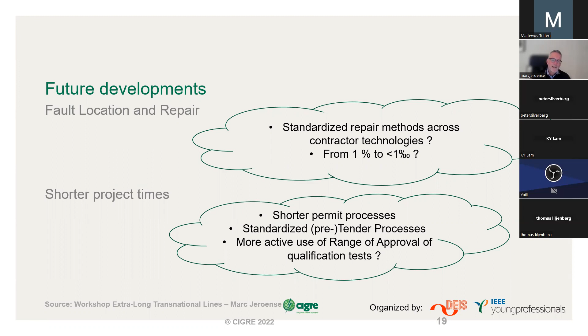I think also what is needed is that the tender processes, the whole discussion between manufacturer and buyer, the TSO that wants to buy a cable system, that whole process can also be streamlined and shortened. Should we make more use of range of approval, not so often doing a pre-qualification test, which takes about 1.5 years including the build-up of the whole system? This is not to say let's forget about QA, QC - that must always be at the same level and even better. But it's still something we should think about.